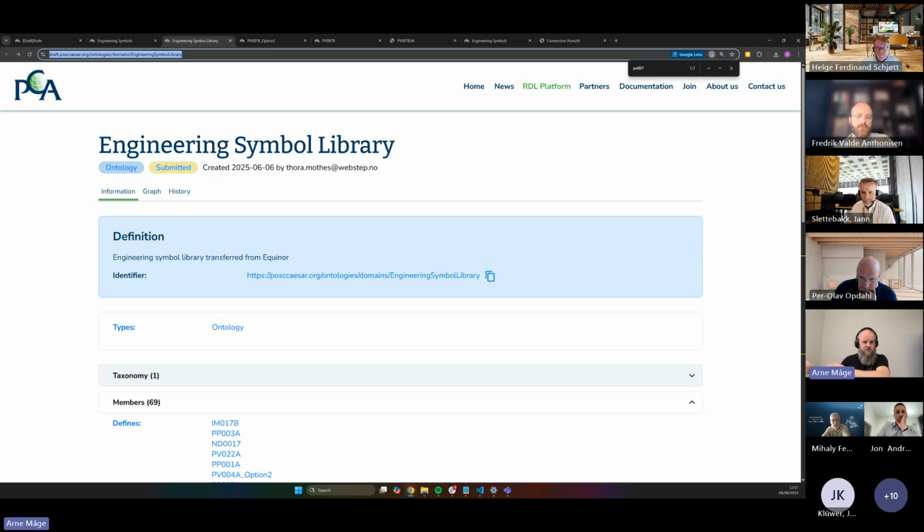We want to keep the P&ID, but we want to drop the diagram, because it's our opinion, and this is an opinion, that the on and off page connector is useful when the only way you have to communicate the process and information is via a static picture. A P&ID has a structured data model backing it, and then it has a picture on the side. We would like to be able to use the structured data only, because that lets us meld two models that are about the same facility seamlessly.